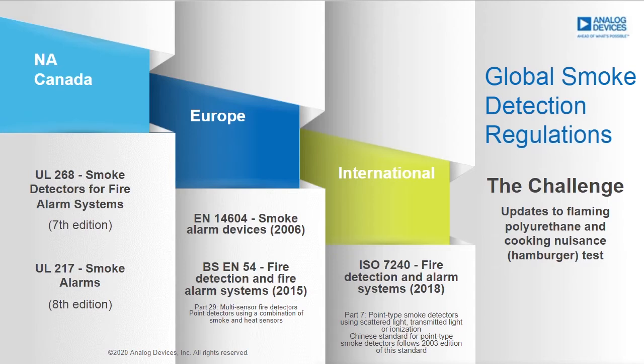In the US and in Canada, there's UL 268, the 7th edition, and UL 217, the 8th edition, both of which are pending. The biggest change in these standards includes updates to the polyurethane flaming and smoldering and cooking nuisance, or what we call the hamburger test. For Europe, there's EN 14604 and BS EN 54, which is the British standard. The piece that's most relevant here is Part 29. For international standards, there's ISO 7240, and the relevant part here is Part 7. And for China, they follow the 2003 edition of ISO 7240.